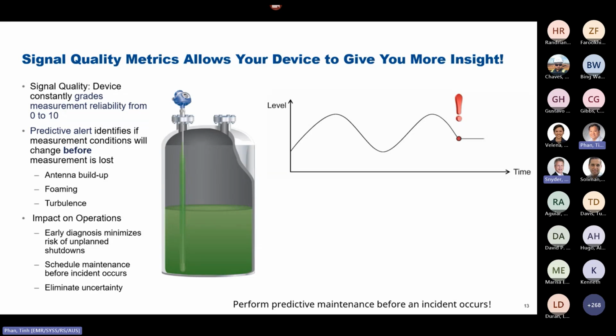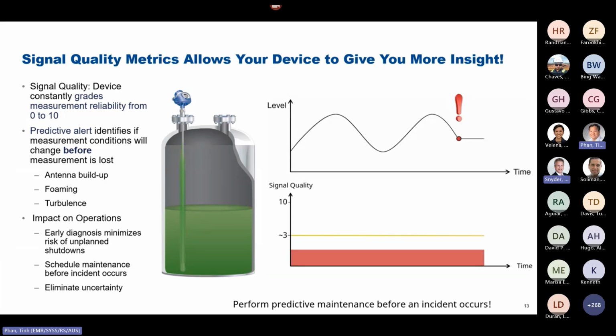You can get buildup, foaming, turbulence, different things happening, and your signal quality starts degrading—so much that you can't control your process anymore because your 4-20 milliamp signal is offset, which can cause a shutdown or a really bad quality batch. If you can get this information early, you can do early diagnostics to prevent unplanned shutdowns, schedule maintenance before an incident occurs, and eliminate uncertainty if you can see this information in front of you in your day-to-day operation.